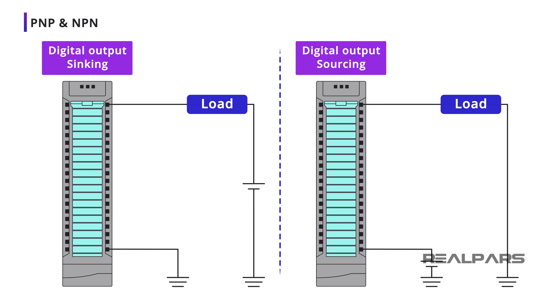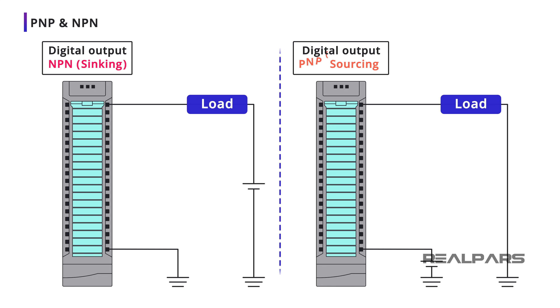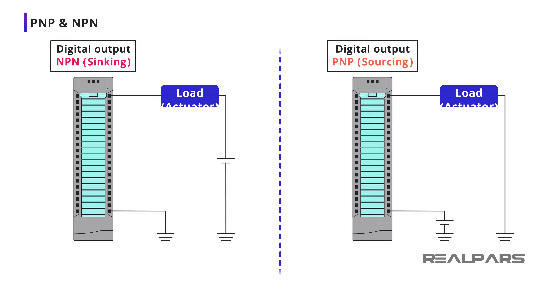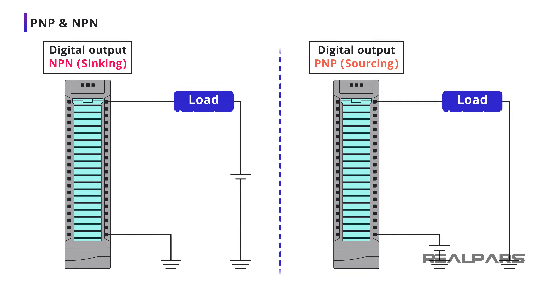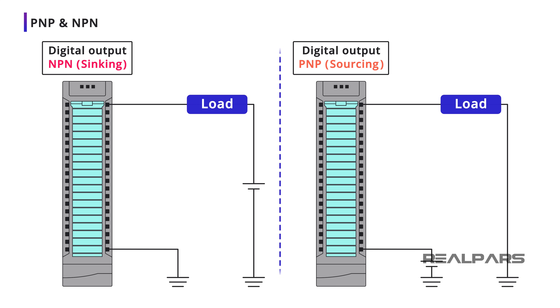Sometimes adding confusion to already murky concepts, some vendors refer to sinking and sourcing outputs as NPN and PNP outputs. You will hear more about NPN and PNP in a later video as we dig into PLC digital input modules and discuss how input field devices are connected to them. We'll explain the reason for the different names. But here's something to remember about output modules: an NPN module is a sinking module, and a PNP module is a sourcing module.